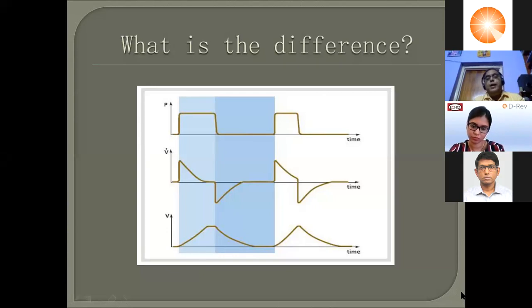As you know, for a controlled breath, how long does the inspiration last? The inspiration lasts for the TI, which you decide. You set a TI and it goes on for that. For a supported breath, how does the ventilator decide how long to continue the inspiration? That depends on something called the flow termination criteria, which is a percentage. It may be 80%, it may be 60%, something like that.